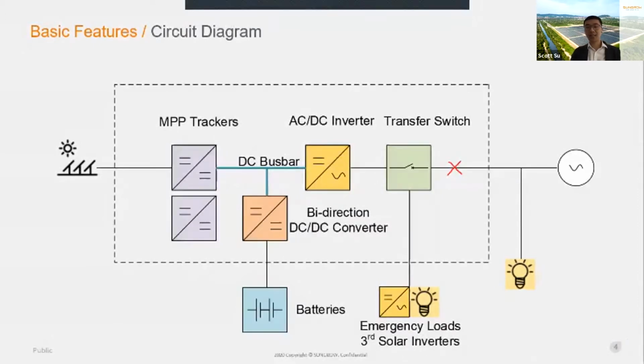So we have the seamless transfer. I will introduce this function later. So firstly, I just want to emphasize what seamless transfer is. When the grid has a power outage, firstly, the transfer switch will disconnect the grid. Secondly, the system will still generate the AC voltage to supply the emergency loads. The whole process will only take 20 milliseconds. So that means most home loads will not lose the power supply.